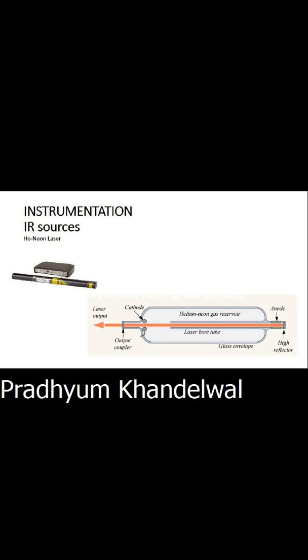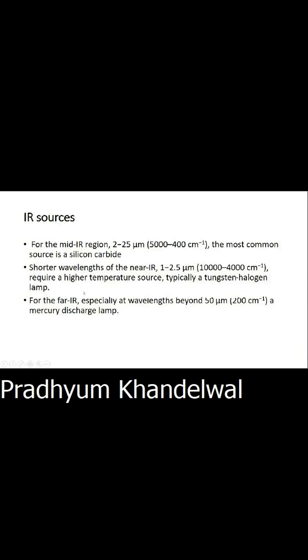Now we will start with instrumentation. Here we use an infrared source, specifically a helium-neon laser. Infrared sources may vary: silicon carbide is used for the mid-IR region, a tungsten halogen lamp is used for shorter wavelengths, and a mercury discharge lamp is used for far infrared regions.